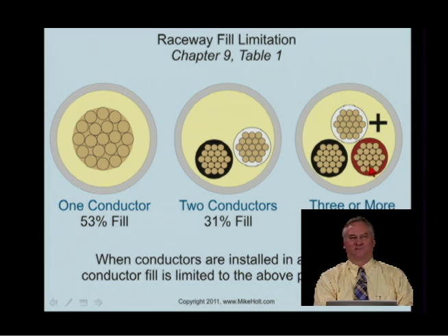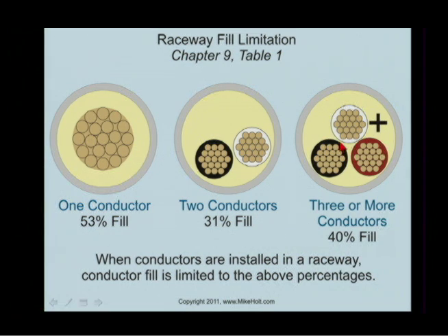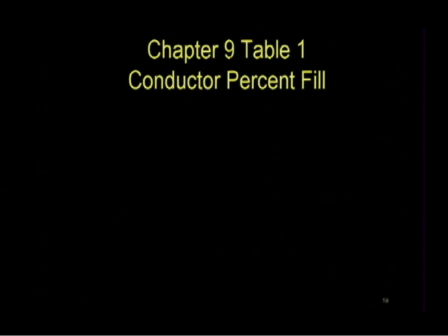But if I go to 3 conductors, you can see that we're now able to use the extra space that wasn't usable with 2 conductors, and we go up to 40% fill. So that gives you some insight as to why we have these different percentages.